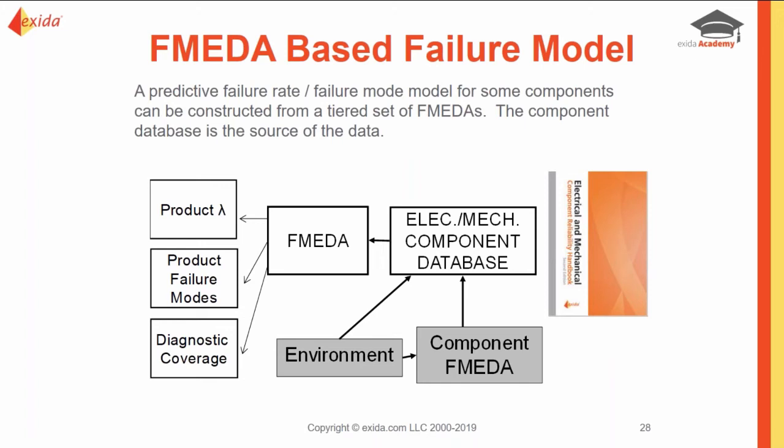The great thing about FMEDAs is they are done for a specific manufacturer for a specific product, down to the specific environment, the specific application, if it's clean or dirty service. All of those variables go into FMEDAs. And the end result, as I said, are failure rates. Those failure rates go into SIL verifications, they go into probability of failure on demand calculations, lots of very important things for your customers, along with the product failure mode and the diagnostic coverage.